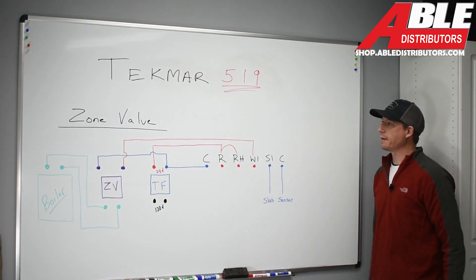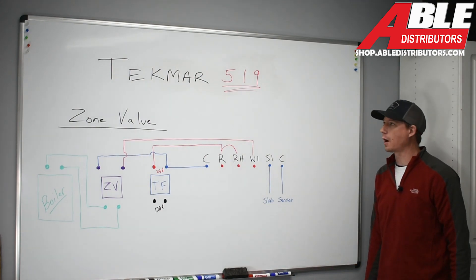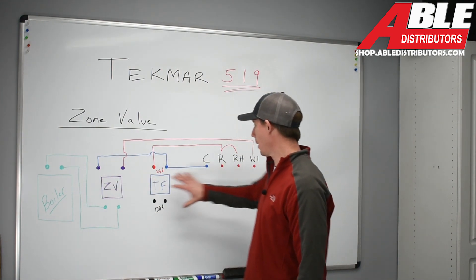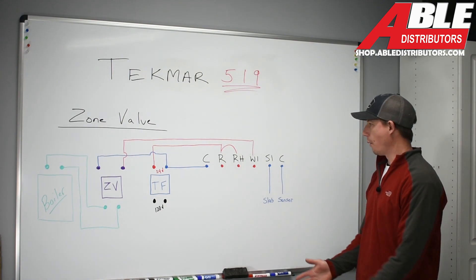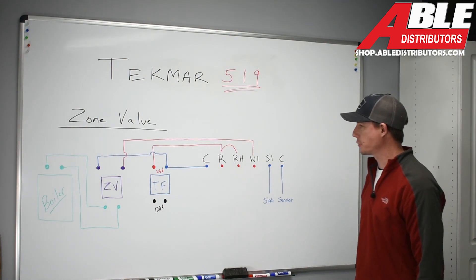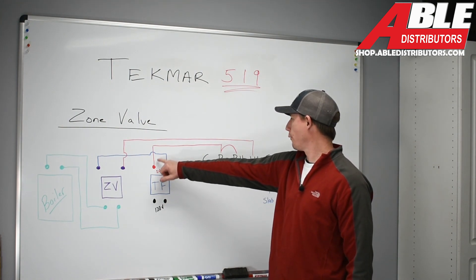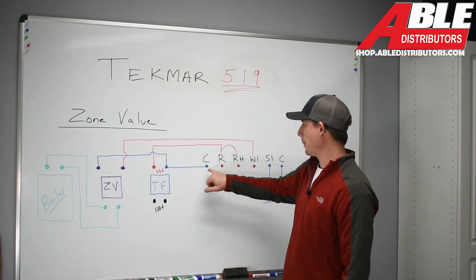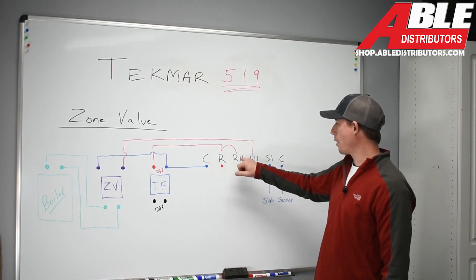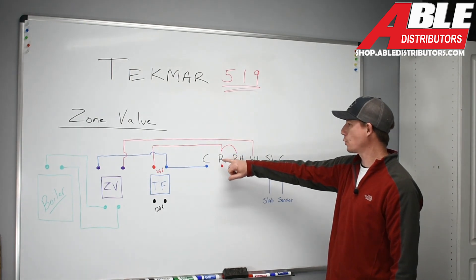Back at the Tekmar 519 — we're going to go through the next couple of videos regarding applications for this control. First, we're going to start with a zone valve application. What we have is a basic 24-volt circuit being applied to this control — it needs 24 volts to power up. Here is our TF, which is our transformer. We have 24 volts coming up to R and a common connection to apply 24 volts to that thermostat at all times.